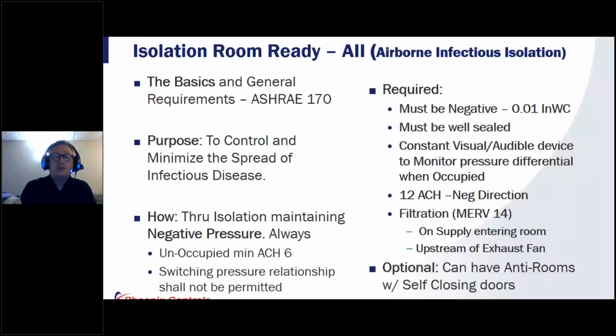But those always have to be maintained in the negative direction, right? Switching pressure relationships is not permitted. A number of years ago they were, but they don't want any more entrainment or any existing or residual outbreaks, or especially if those spaces were to have been used for an immune deficient patient, right? So they don't want to be able to switch from negative to positive or positive to negative, just given the residual, right? So these isolation spaces, AII spaces, are now dedicated to negative pressure always.